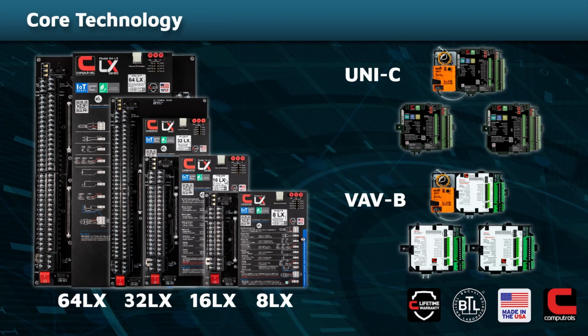The VAV-B comes in at a slightly lower price point. It's what we call application specific, meaning it's hard-coded for VAV and fan coil functionality. One advantage is that because it's simpler in terms of programming, it's also available with a variety of third-party protocols: Siemens FLN, Computrols, BACnet, Johnson Controls N2. That means when you integrate using our product, you'll be able to change VAV controllers from that third-party manufacturer as they fail, one at a time. You don't have to completely retrofit or gut the floor to switch from old technology to new. It's very attractive to owners, very comforting when they can transition to our hardware with that lifetime warranty.